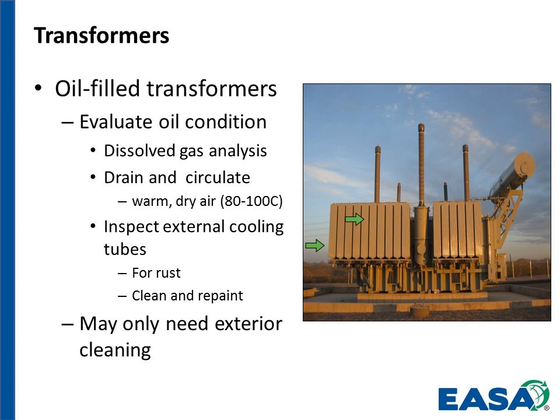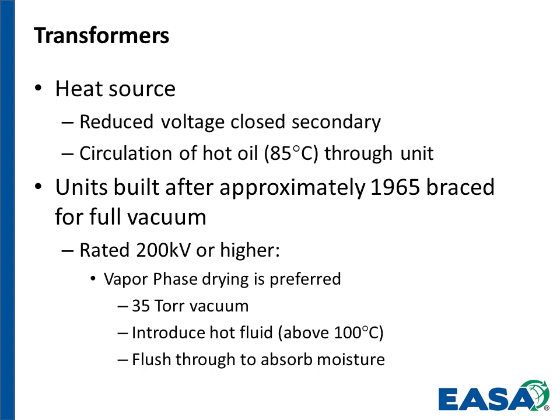Transformer oil is expensive, and it's one more thing to ship in, but it's a routine process for the large transformer rebuilders to run a special filter and circulate the oil through the special filter to remove moisture. So if we look at the next slide, we can use a heat source to dry the transformer. A very popular way to dry a large transformer, the one in the picture previously, is to circulate hot oil through the unit. So heating the oil to approximately 85 degrees C, circulating hot oil through the transformer should flush out and remove the moisture. So that's a pretty easy fix.